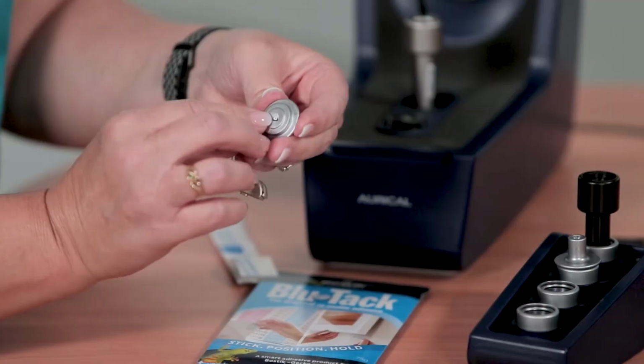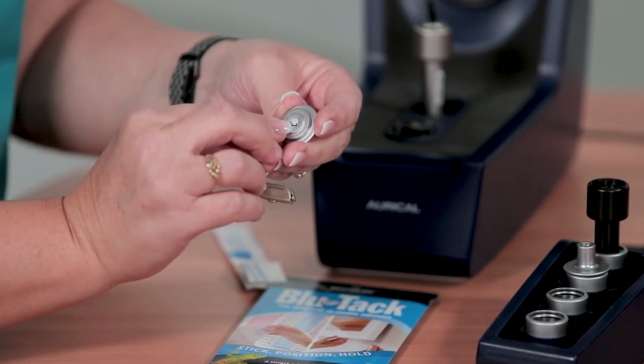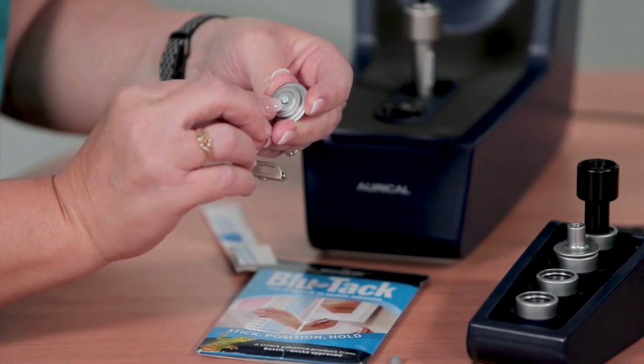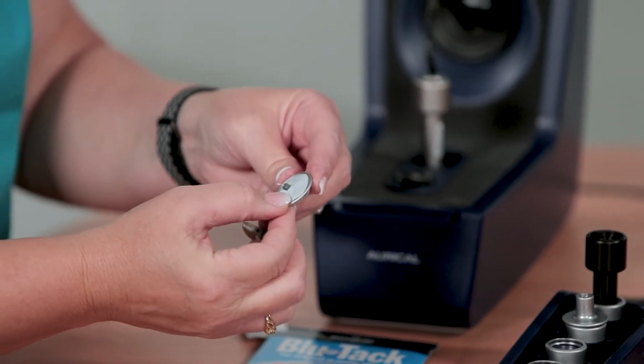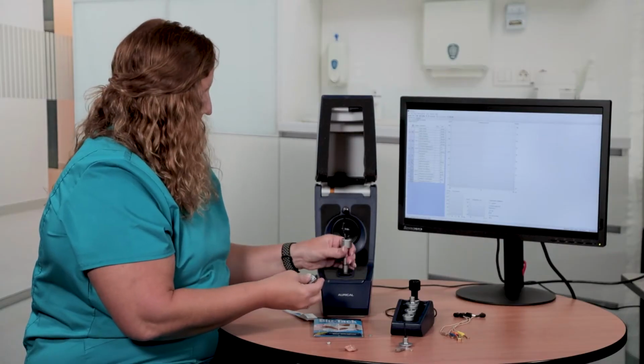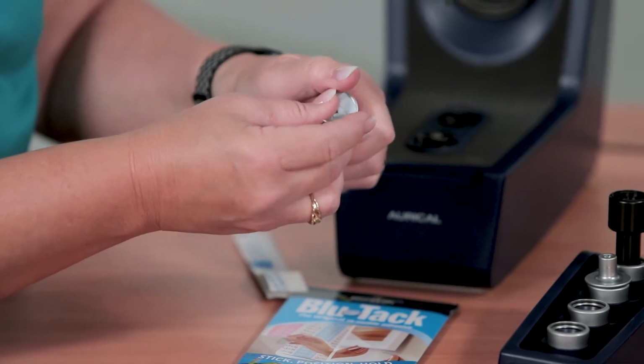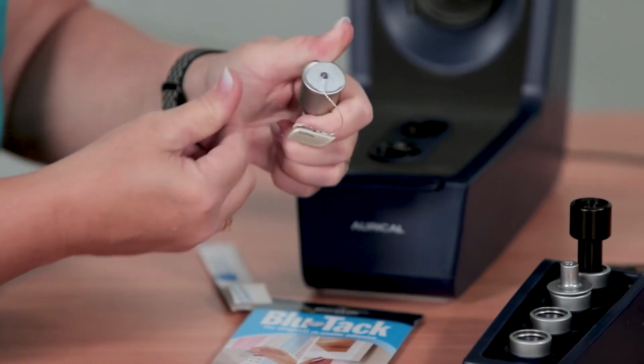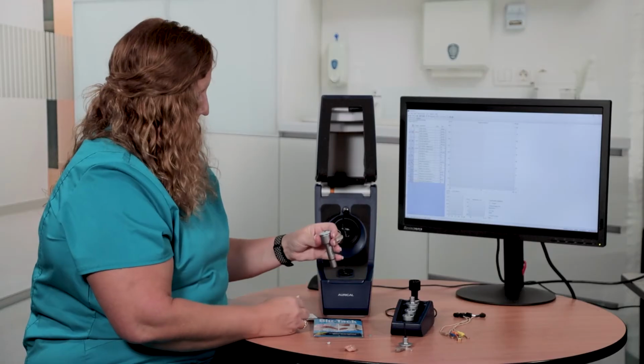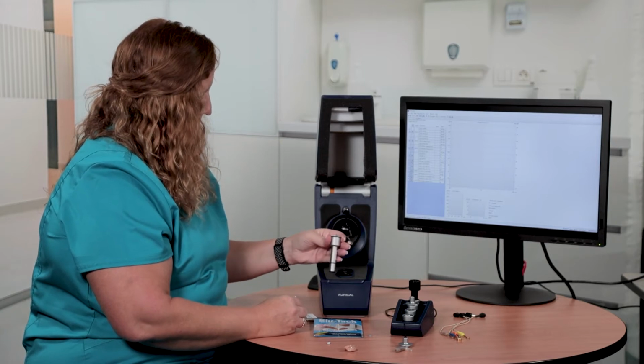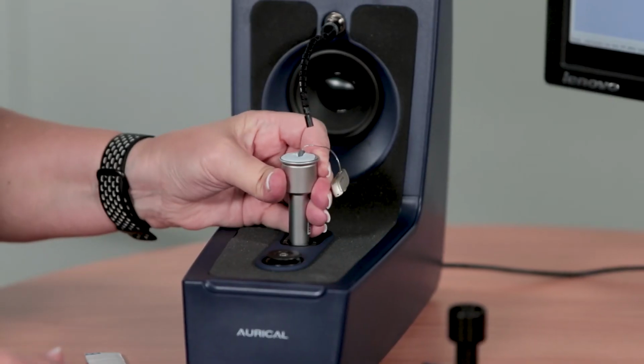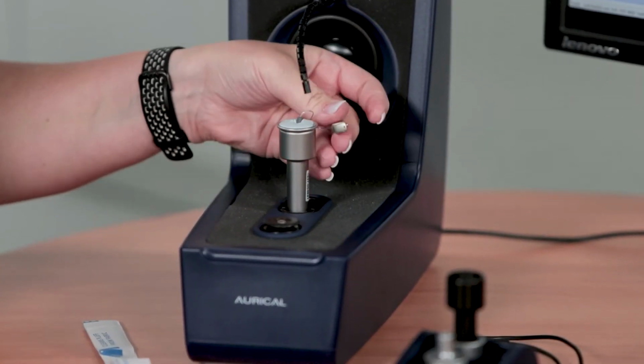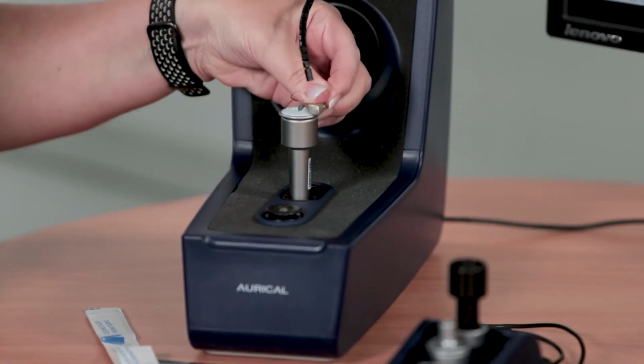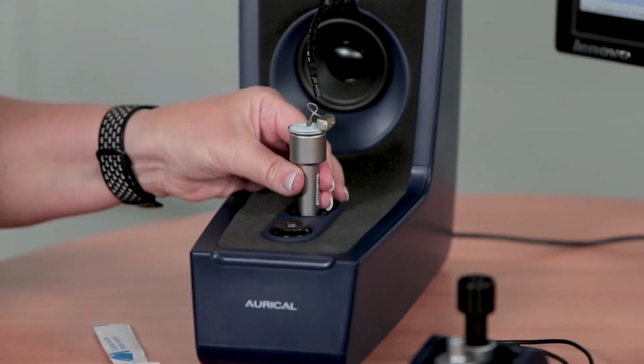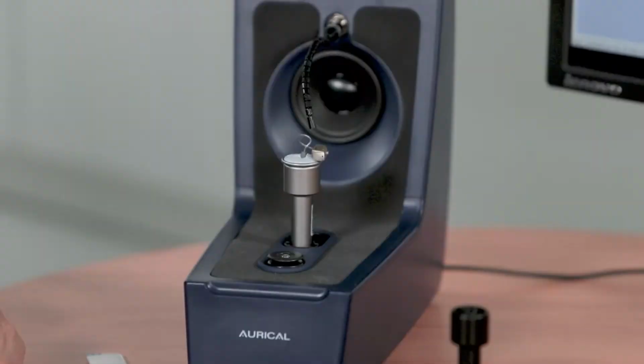Check that the opening in the middle of the adapter is clear of putty and the acoustic opening of the hearing aid is clear. Snap the adapter into place on the coupler cavity. Place the coupler microphone in the microphone port furthest from the Aurical HIT speaker, the raised microphone port, so the position of the hearing aid is level with the center of the Aurical HIT speaker. Position the hearing aid with the front-facing microphone directed at the Aurical HIT speaker.